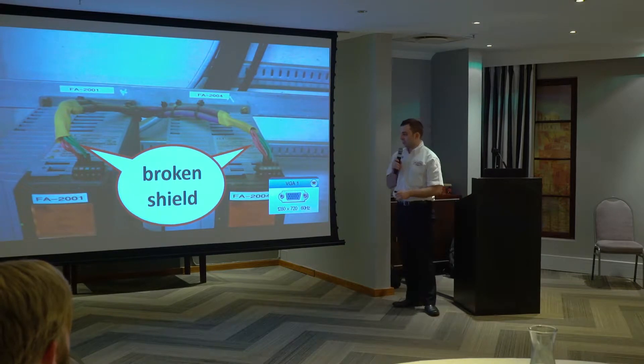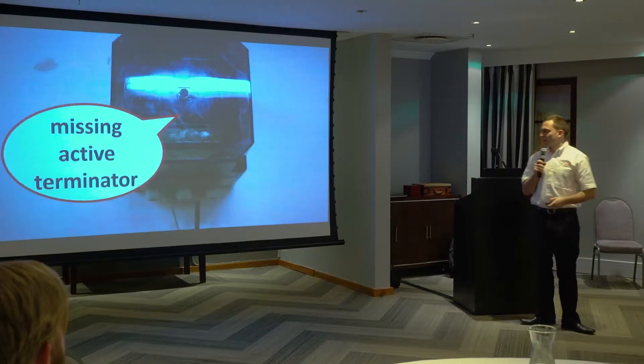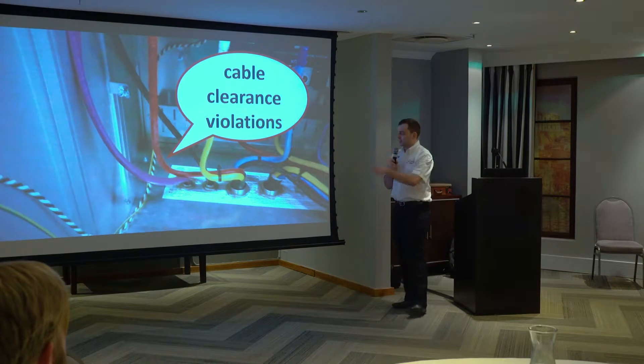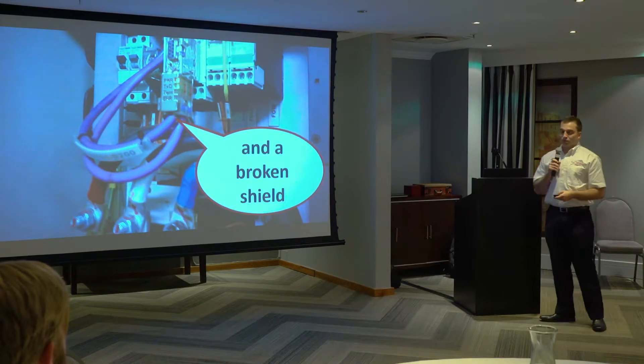First things first, we find some installation issues. Broken shields between devices - if you don't know why that's a problem, come to training. Missing active terminators - also come to training. Cable clearance violations, more cable clearance violations - this is my favorite one. Also, a broken shield.